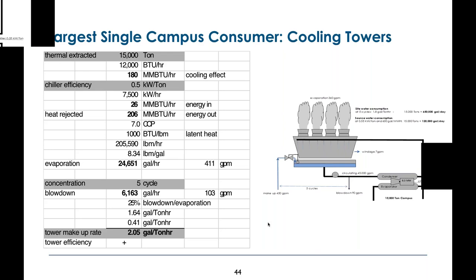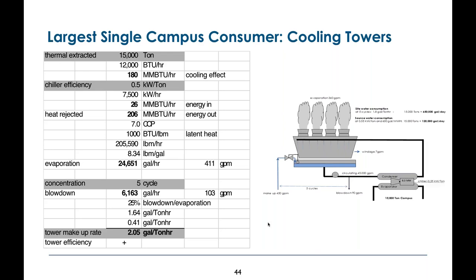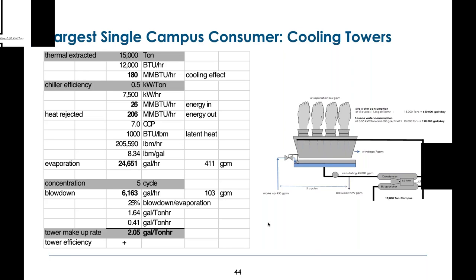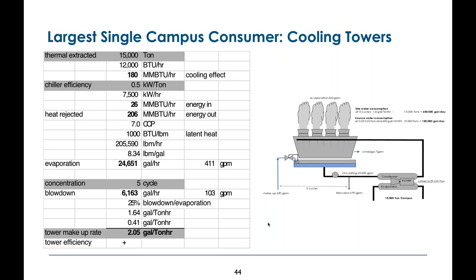The total amount of heat you're pumping out of the cooling tower is a combination of the heat you're extracting from the campus plus the heat of compression, the energy you're putting into the chiller to get the heat out. That turns out to 206. Now, if you convert that total amount of BTUs we're dumping out the cooling tower into water, that turns into 24,000 gallons an hour to get 15,000 tons out.